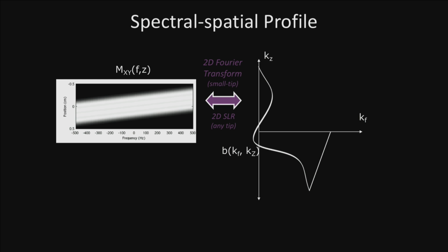We approximately take a Fourier transform of this pattern, which is defined by our RF pulse and our gradient. Our gradient tells us where we're going, and our actual RF tells us what the pattern is. We can take a Fourier transform, more or less, of this and derive the spectral and spatial response of our RF pulse.